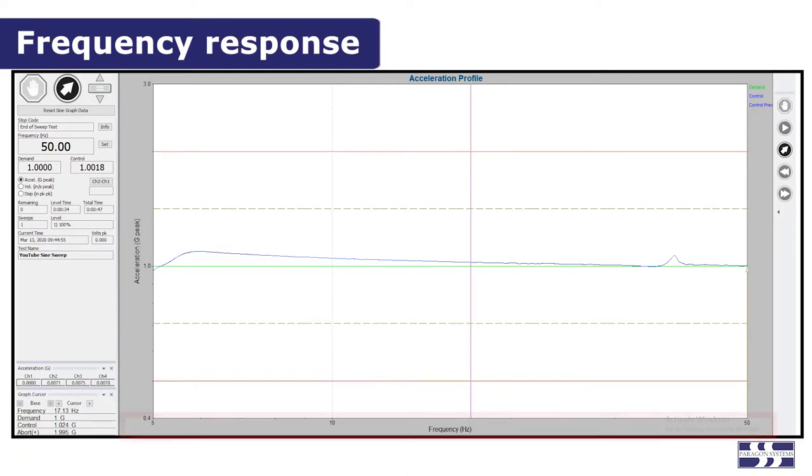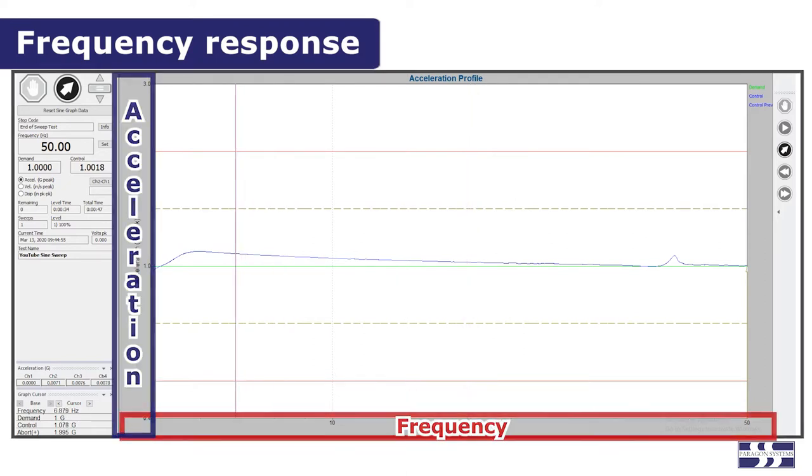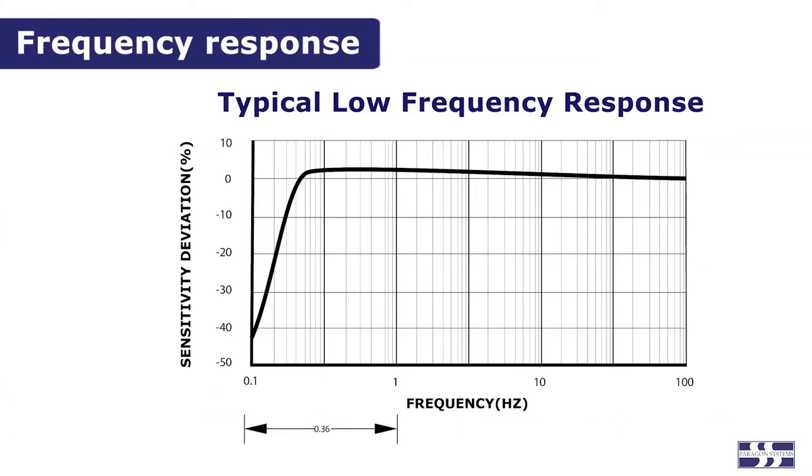Accelerometers are designed to measure acceleration accurately over a range of frequencies. Some are optimized for lower frequencies, even down to DC levels. Others are good at measuring very high frequencies, but can't accurately measure below 2 Hz.